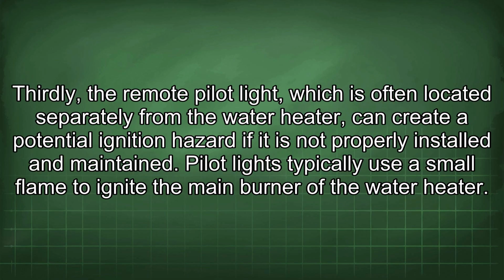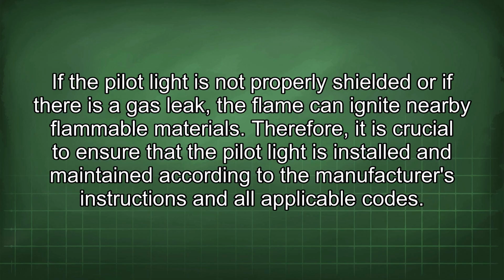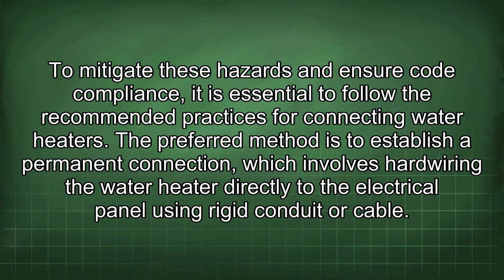Thirdly, the remote pilot light, which is often located separately from the water heater, can create a potential ignition hazard if it is not properly installed and maintained. Pilot lights typically use a small flame to ignite the main burner of the water heater. If the pilot light is not properly shielded or if there is a gas leak, the flame can ignite nearby flammable materials. Therefore, it is crucial to ensure that the pilot light is installed and maintained according to the manufacturer's instructions and all applicable codes. To mitigate these hazards and ensure code compliance, it is essential to follow the recommended practices for connecting water heaters. The preferred method is to establish a permanent connection, which involves hardwiring the water heater directly to the electrical panel using rigid conduit or cable.